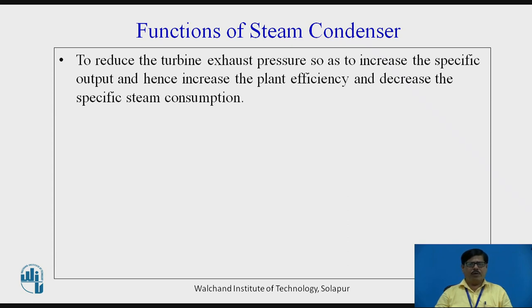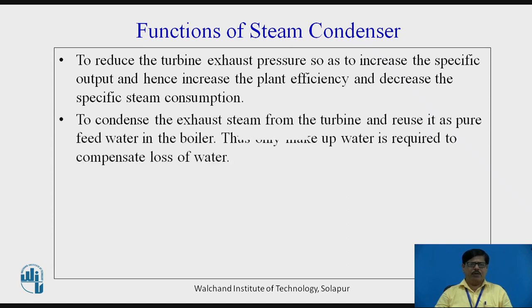It also gives the advantage that the amount of steam required to produce 1 kW of power will decrease. That is, for the same size of the plant, we will require less steam flow rate — the specific steam consumption will decrease when we use a steam condenser. Another function is to condense the exhaust steam from the turbine and to reuse it as pure feed water in the boiler. The exhaust steam is condensed back into water, which we call condensate. This condensate being pure, we can reuse it again and again as feed water in the boiler, only requiring makeup water to compensate for any losses.